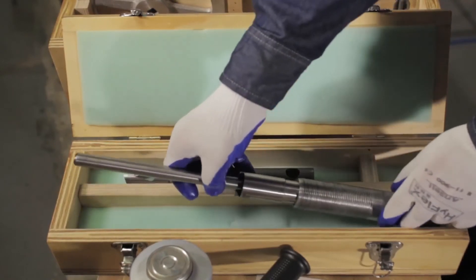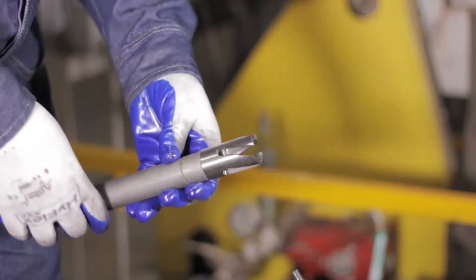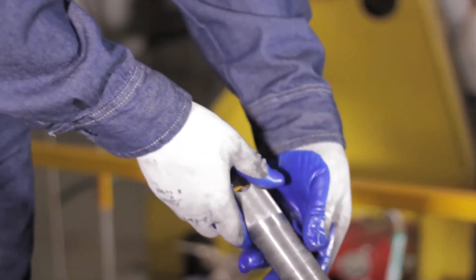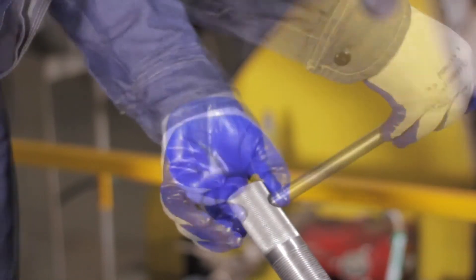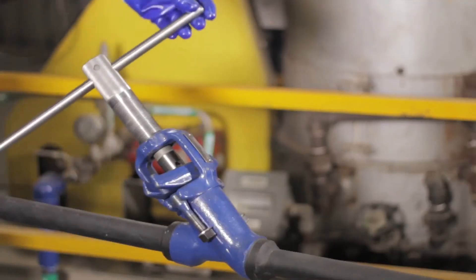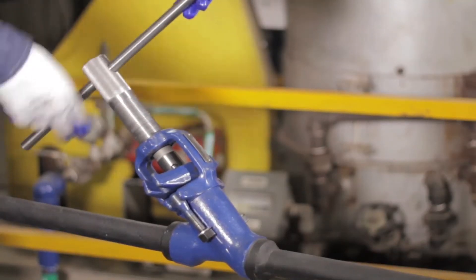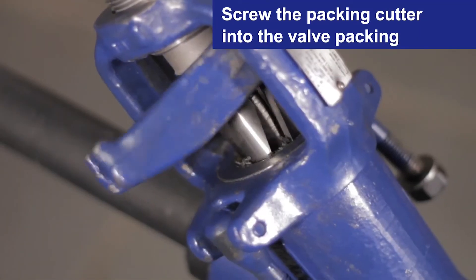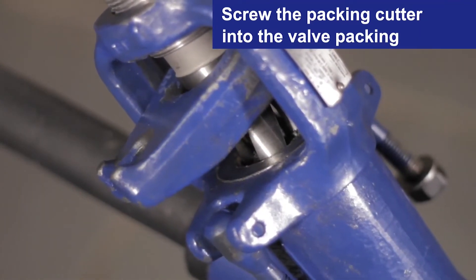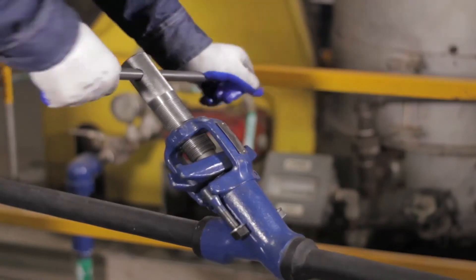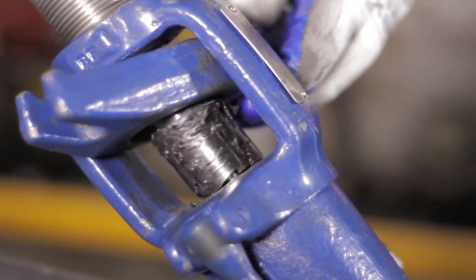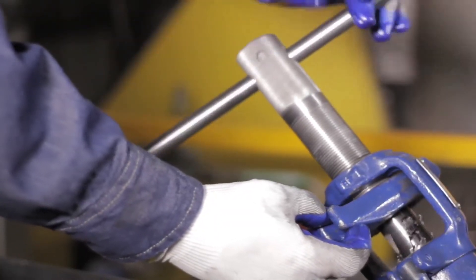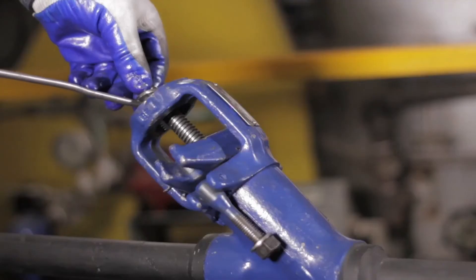This packing cutter is inserted along the stem until it comes to rest against the packing. Next, the tool guide is inserted over the packing cutter and screwed into the yoke threads. These tools are all supplied as part of the kit for renewing valves. The guide is inserted into the yoke until the holes of the guide and the cutter are lined up. The pry bar is inserted into the holes. Now the packing cutter can be screwed into the valve packing. When the cutter can no longer turn freely, it has become filled with the packing material. You can now back out the tool. You will probably have to use the cutter one or two more times to remove all the packing from the valve.